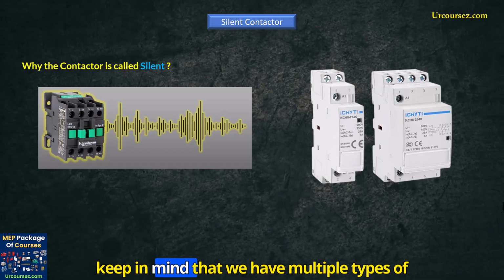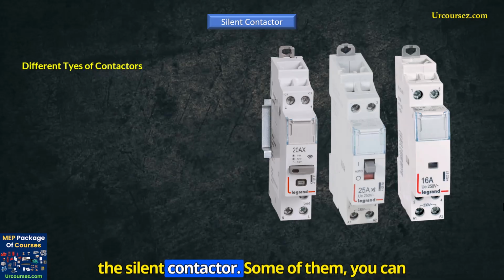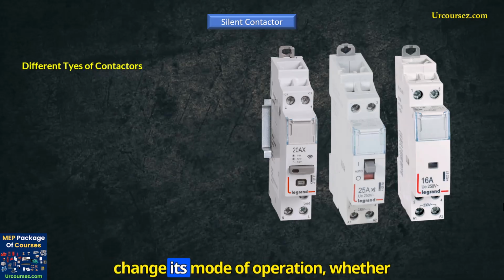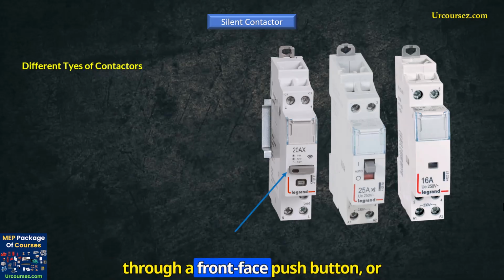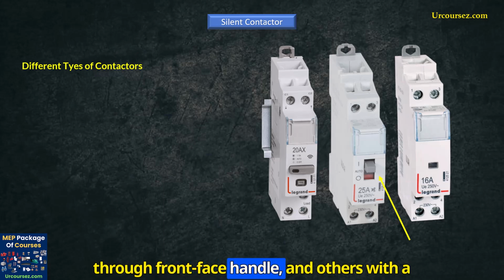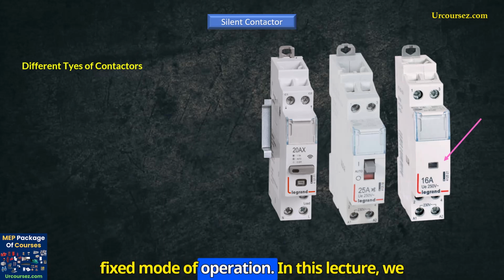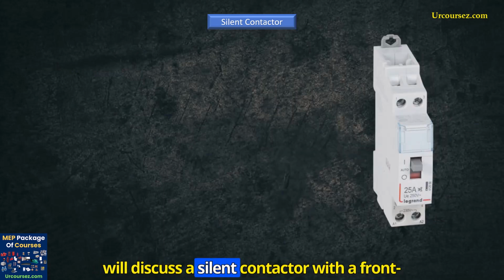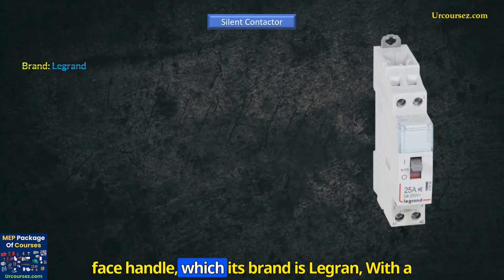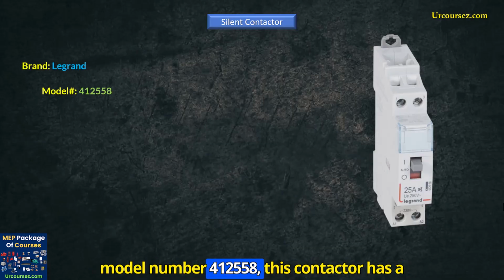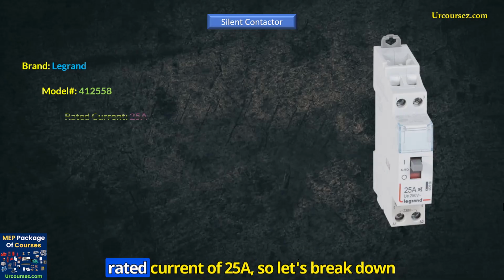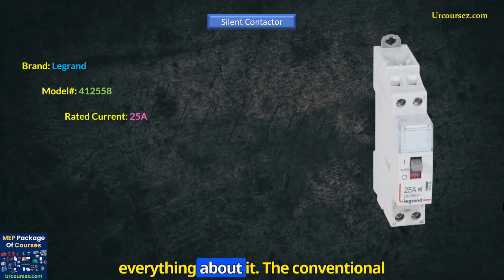But you need to keep in mind that we have multiple types of the silent contactor. Some of them you can change the mode of operation, whether through a front-face push button or through a front-face handle, and others have a fixed mode of operation. In this lecture, we will discuss a silent contactor with a front-face handle, whose brand is Legrand, with model number 412558. This contactor has a rated current of 25 amperes, a silent power contactor. So let's break down everything about it.